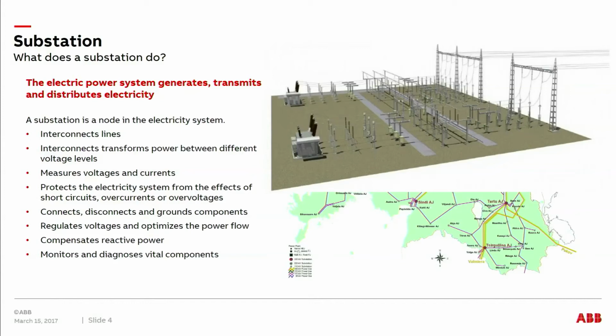And if you're looking into the substation, what does a substation do at the end of the day? A substation interconnects lines, so you can switch a line on or off. Therefore, in a substation you will have disconnecting circuit breakers or disconnecting switches. You can also earth or ground a line so that you can do work on it—therefore it has to be earthed, so there is grounding equipment in the substation.